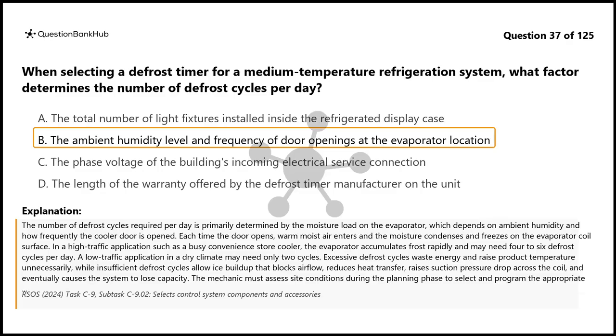Excessive defrost cycles waste energy and raise product temperature unnecessarily, while insufficient defrost cycles allow ice buildup that blocks airflow, reduces heat transfer, raises suction pressure drop across the coil, and eventually causes the system to lose capacity. The mechanic must assess site conditions during the planning phase to select and program the appropriate defrost schedule.